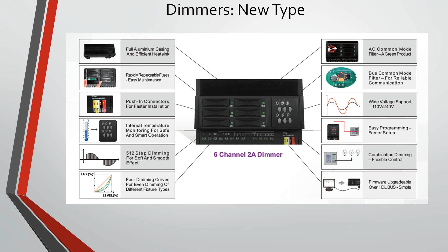There are 3 types: 6 channel 2 amp, 4 channel 3 amp, and 2 channel 6 amp each. There is also a 0-10 volts device. It has 6 channels for relays and 6 channels for 0-10 volts. They work only together. So channel 1 relay will only work together with channel 1 0-10 volts. You will not be able to use it as 2 separate devices. They usually control lighting ballasts for fluorescent, usually. HDL also produces 0-10 volts ballasts.